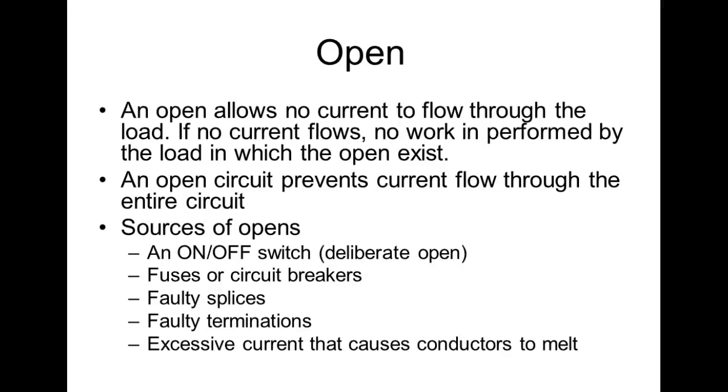Our problems, of course, are faulty splices, faulty terminations, and then, of course, conductors breaking. They break every once in a while. People will put them under stress. We were redoing something on the little Mitsubishi robot last semester, and to do it, we had to take it up and take it off the line and put it on a table.